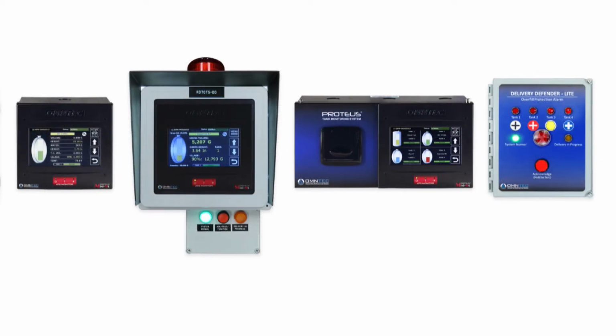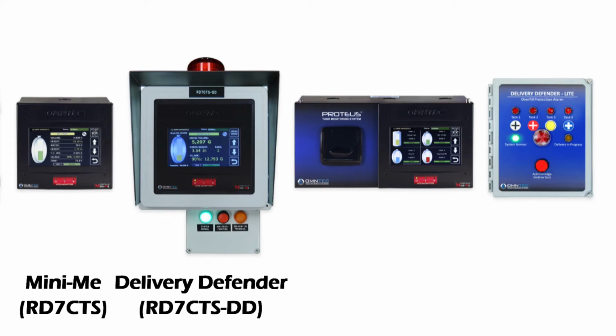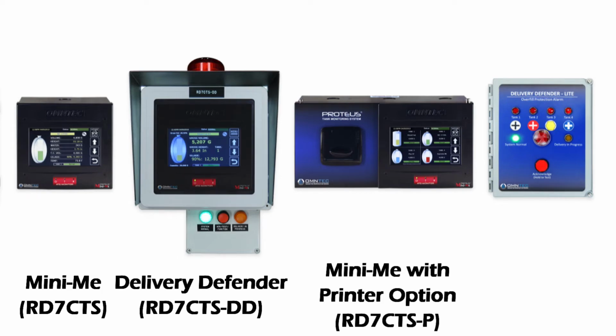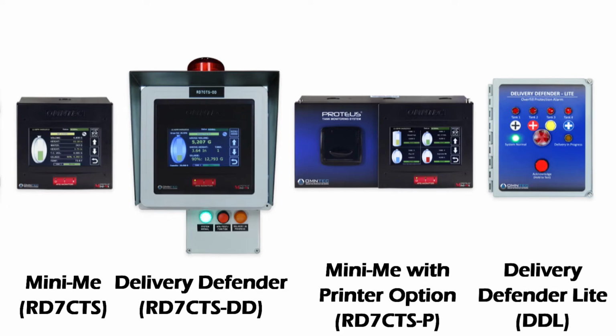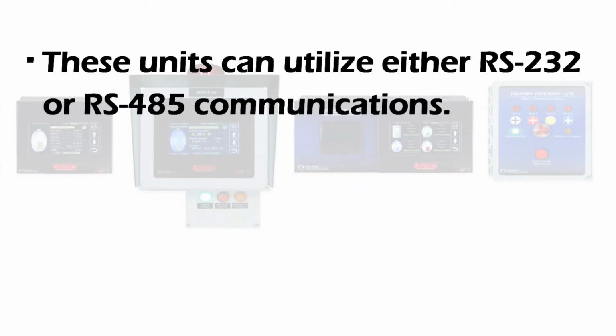For remote displays, such as the Mini-Me, RD7CTS, Delivery Defender, RD7CTS-DD, Mini-Me with printer option, RD7CTS-P, or the Delivery Defender Lite (DDL), the problems are most often wiring or communication issues. However, internal remote display problems are possible. These units can utilize either RS-232 or RS-485 communications.